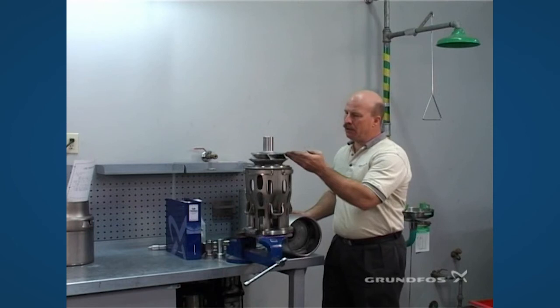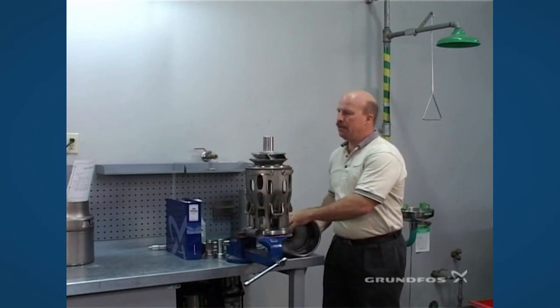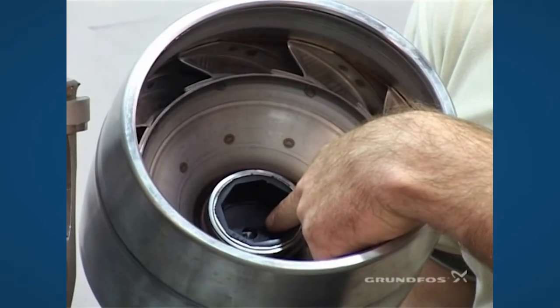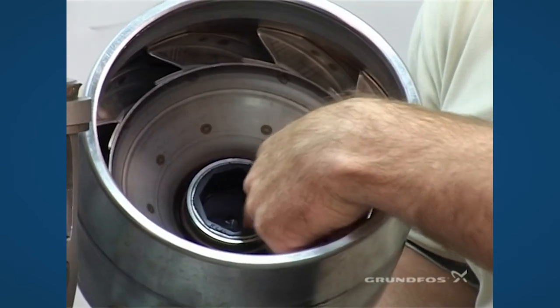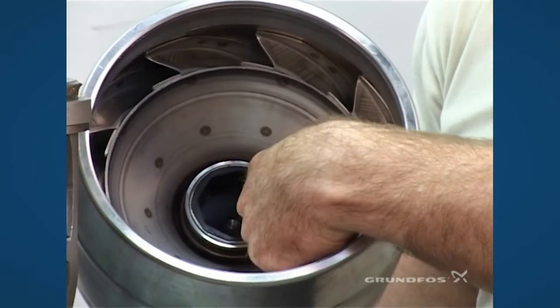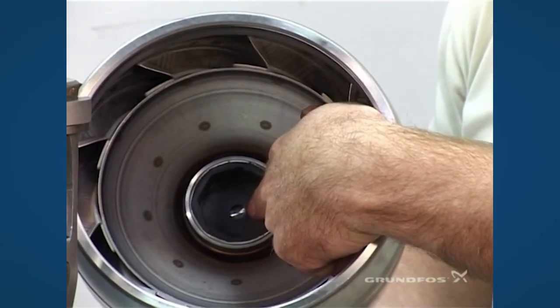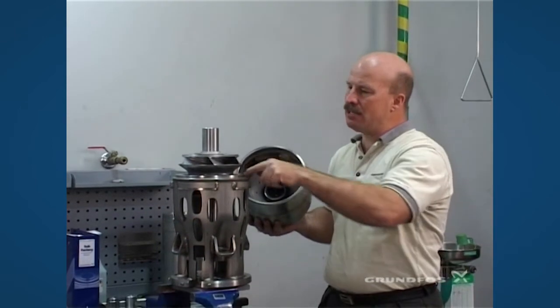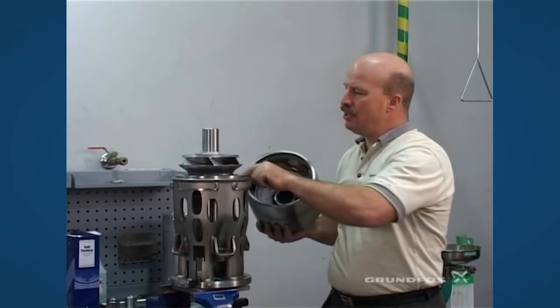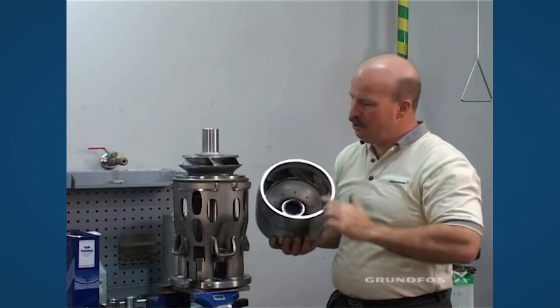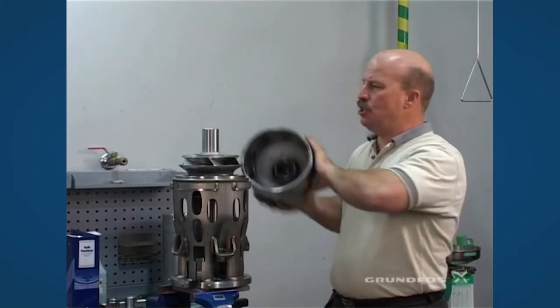After finishing the torque on the split cone nut, we can add the upper chamber. Just like the 625 and 800S, it has the thrust washer all the way down inside in the chamber itself. This is placed onto the inlet. Make sure that the inlet area is clean and free of burrs and the same holds true for the seating surface of the chamber.